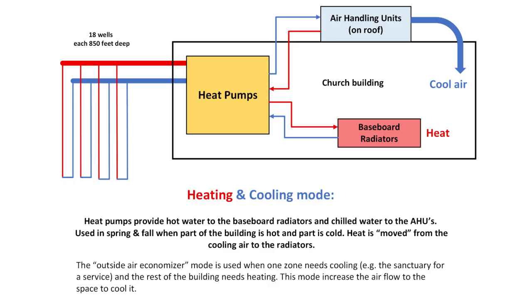Interestingly, this works very efficiently. If we cool the air in the rooftop units, there's cool water going to those units and warm water coming back, since it absorbed the heat out of the air. Instead of sending that warm water back into the ground, we turn it around and pump it over the baseboard radiators. The radiators give off the heat, cooling the water, which then goes back up to the air handling units. So in this mode we're actually moving heat from one side of the building to the other, only adding or subtracting from the ground what's needed if the amounts don't match. Instead of generating heat, we're simply moving nature's heat to different parts of the building—it's a great concept and another big advantage of the geothermal system.